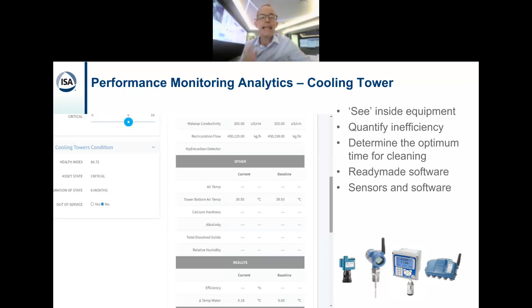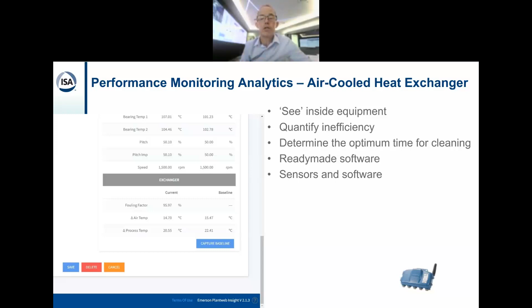Air-cooled heat exchanger fouling can occur on both the air side fins and tube side, reducing the efficiency, again driving up energy consumption. Now, using data from additional sensors, the software computes a fouling factor. This information is used to determine the optimum time for cleaning in order to improve sustainability while minimizing the downtime for cleaning and, in this case, can also be pinpointed to specific cells.